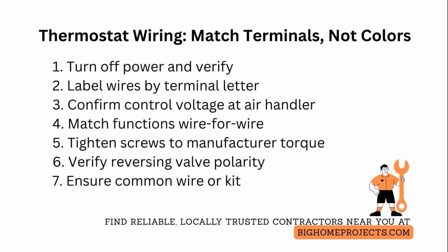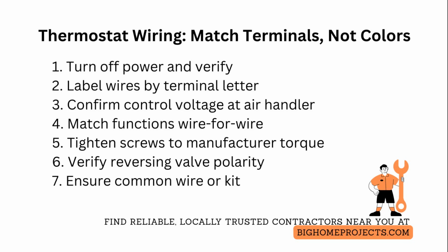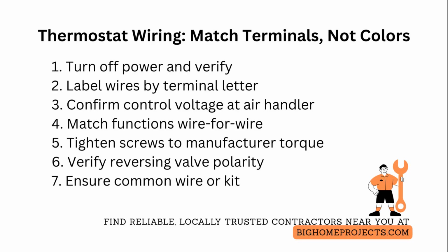Map functions wire for wire: heating call, cooling call, fan, common, auxiliary heat, compressor lockout, and any two-stage or communicating lines. If a wire is unused, cap it and leave it isolated. Never repurpose a conductor without updating both ends and the control board.